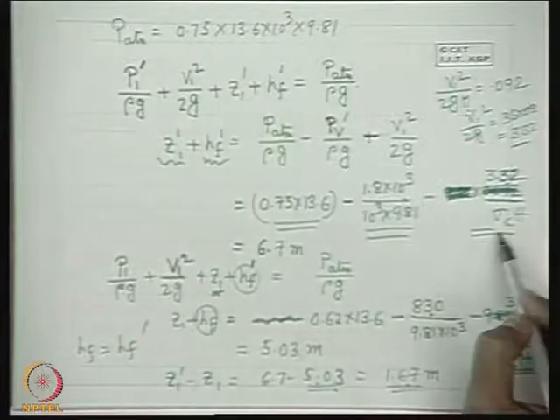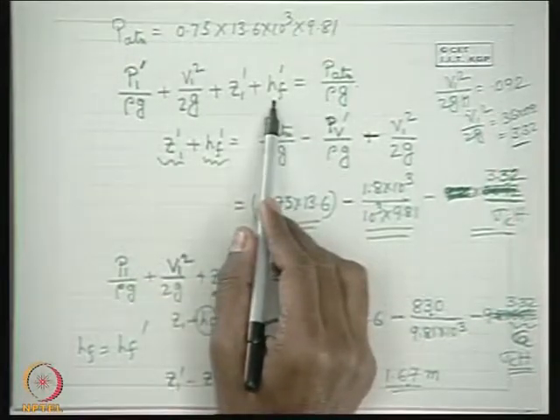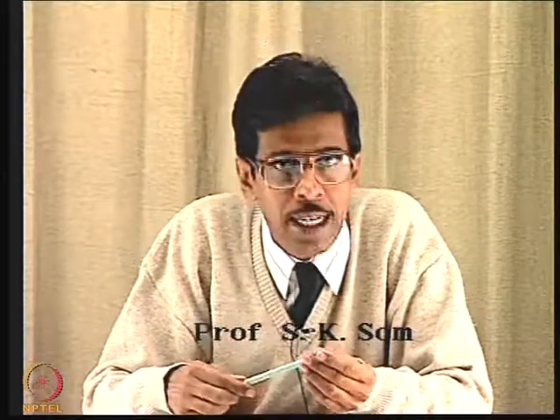This demonstrates how we use the cavitation parameter σ_c and Bernoulli's equation between the pump impeller inlet and the sump free surface to determine the maximum allowable height above the sump at which the pump must be placed — ensuring the minimum pressure at the impeller inlet remains above the vapor pressure of the working fluid at the working temperature. Thank you.